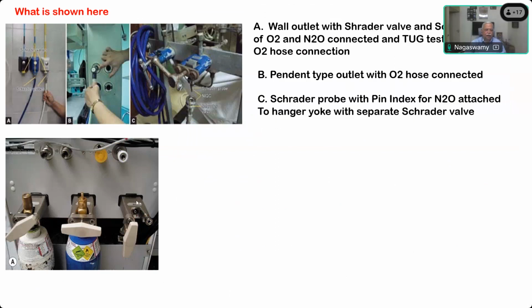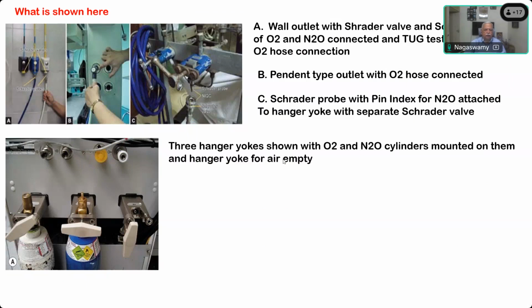Okay, so 3 hanger yoke assemblies, and it is written here very faintly, if you can see closer, air. So that air connection is not given, but nitrous oxide and oxygen are there. And here there are other connections also on the back. Okay, so this is the back side of a newer anesthesia workstation where spare cylinders can be attached. So 3 hanger yokes are seen, with oxygen and nitrous oxide cylinders mounted on them, and the hanger yoke for air is empty. So here it is written air, and it is written empty.